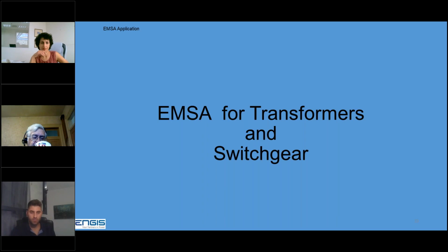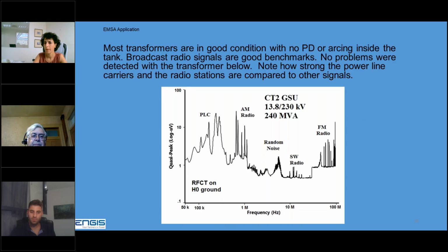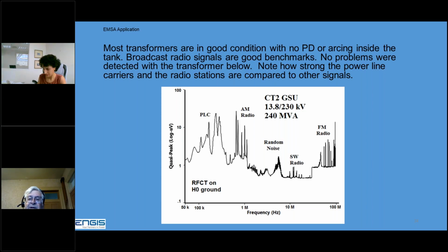EMSA for transformers and switchgear. Most transformers are in very good condition. There's no PD or arcing inside the tank. Since they're connected to the grid, you have long transmission lines, so you pick up a lot of radio signals. And these are good benchmarks to whether there is or is no problem.